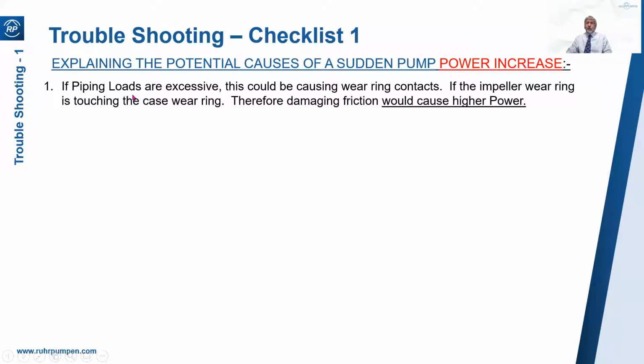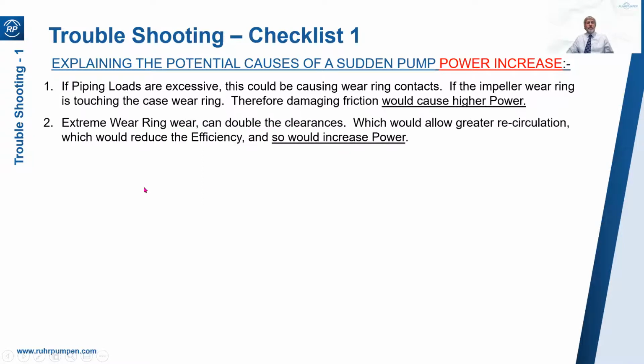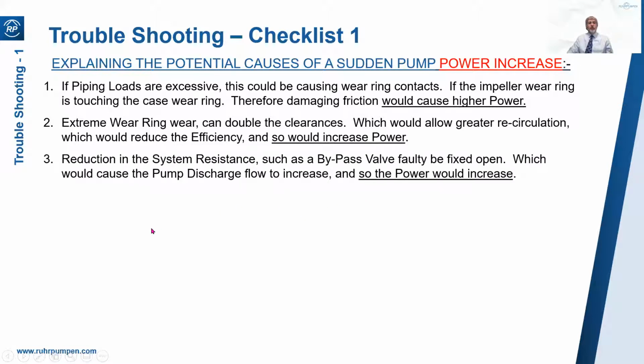Firstly, piping loads. If the piping loads are excessive, you could be distorting the case and causing wear ring contact. So if the impeller wear ring is touching the case wear ring, you're going to get rub, damage, and higher power, as well as vibration. Secondly, extreme wear ring wear. Your clearances will open up, they might be double, and this allows greater recirculation, hence reducing the efficiency and increasing power again. Third thing to look at is your system resistance curve. Maybe there's a bypass valve that's fixed open. So the pump discharge flow has increased. If you're increasing your flow, your power will increase.